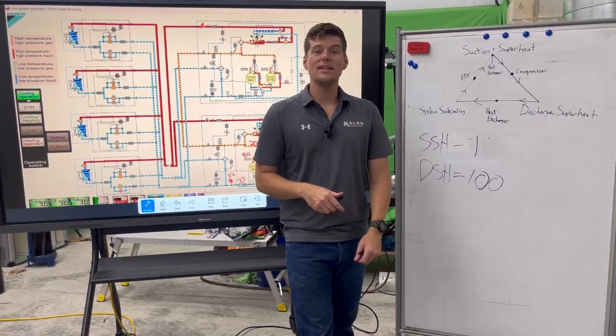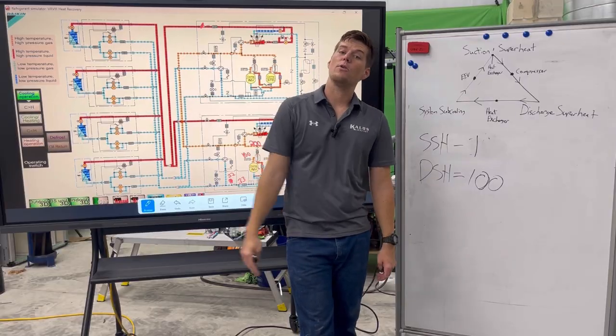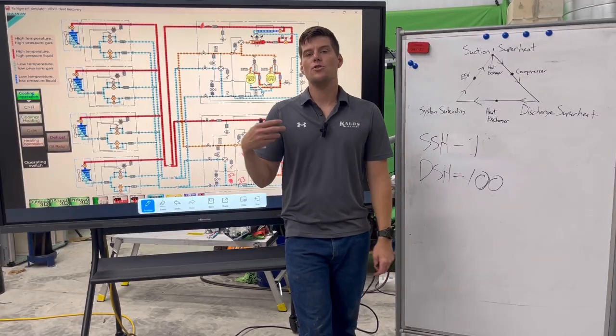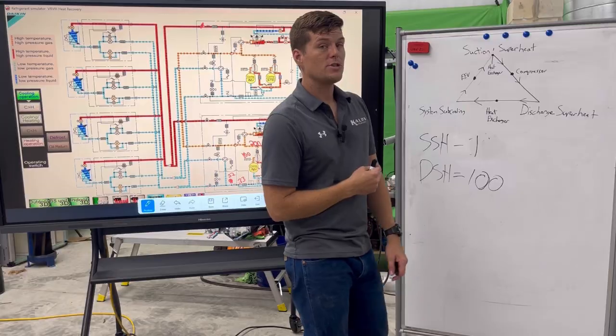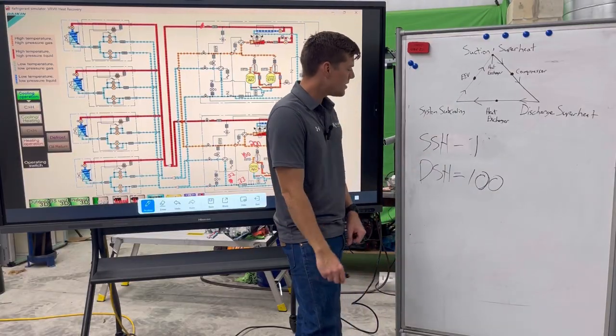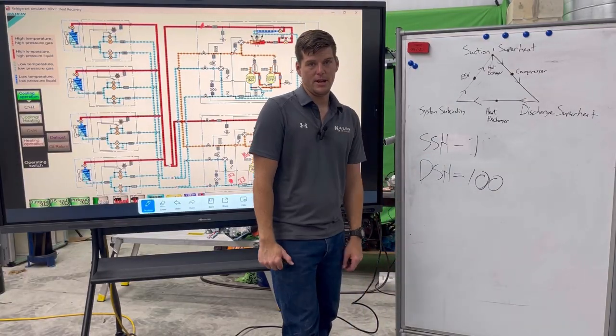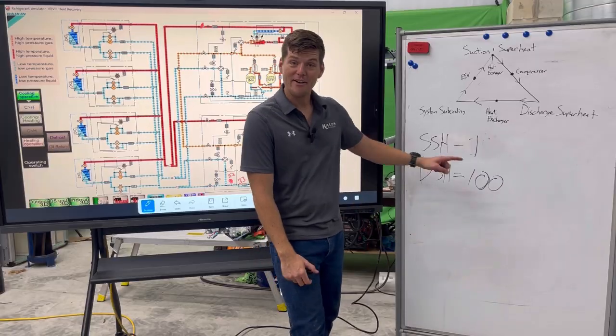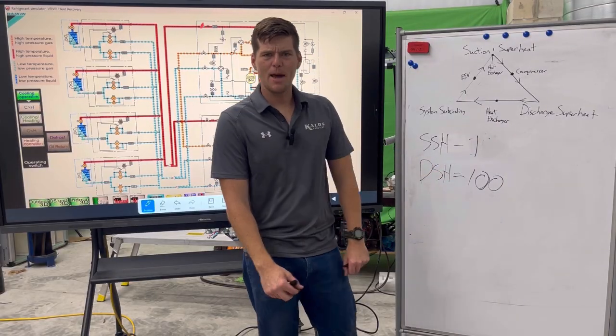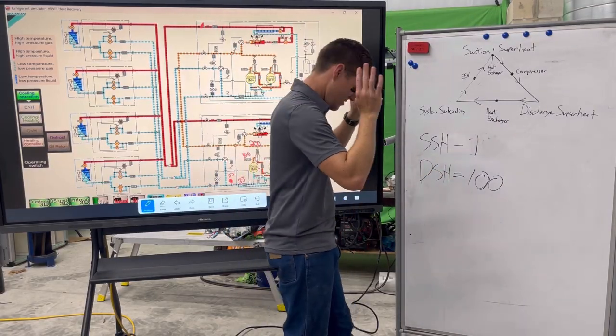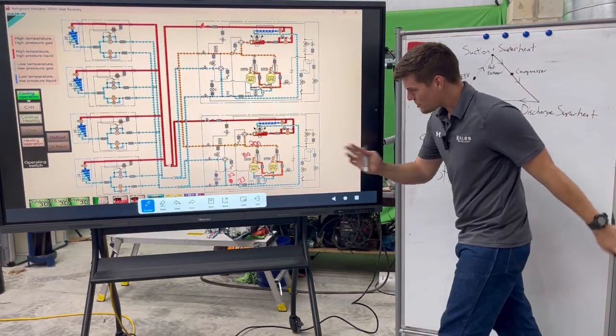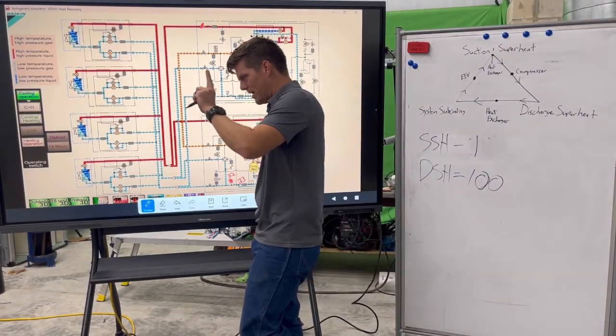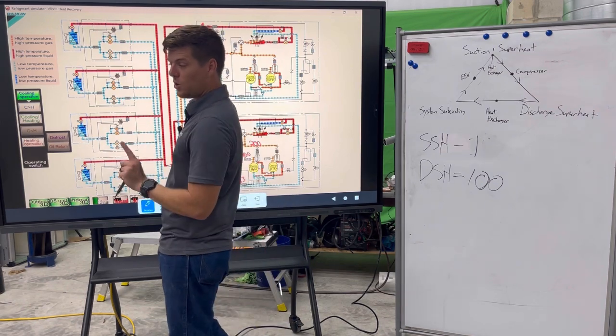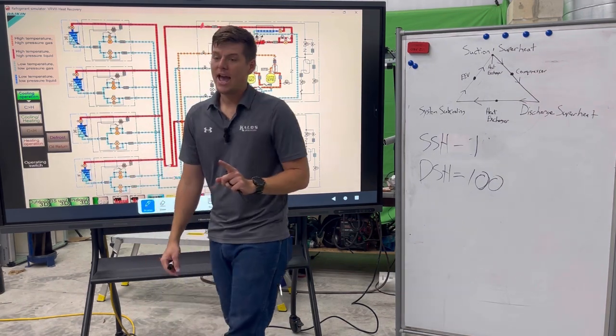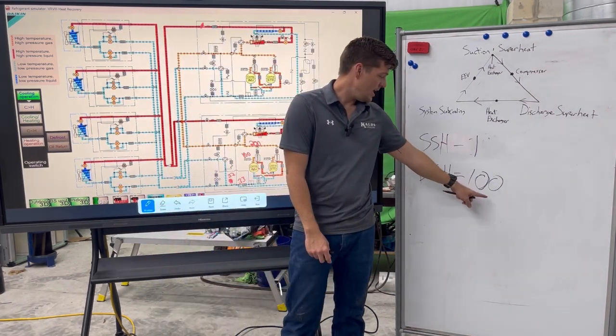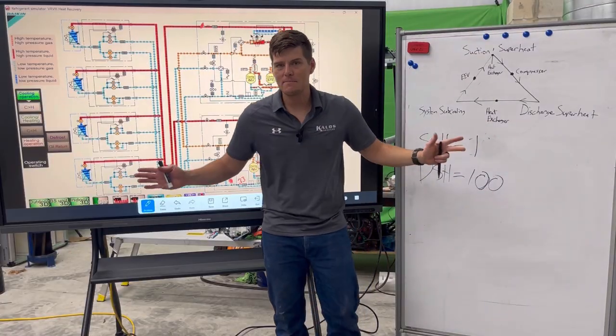So what I like to see is a nice level, even number within an hour, 2 hours, no drastic changes in the system. Those are the numbers that I'm looking for. And so 1 suction superheat, 100 discharge superheat. Now, could this actually happen? And I have actually seen this. Why would this happen? Whoa. You're telling me right now that if my suction superheat is 1 degree and I've got close to liquid coming back to my compressor, and yet my discharge superheat is 100 degrees, how does that make any sense?